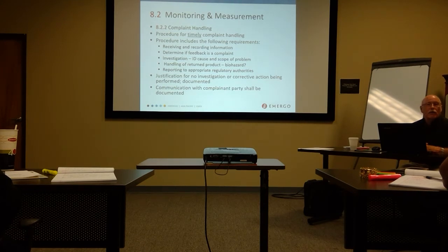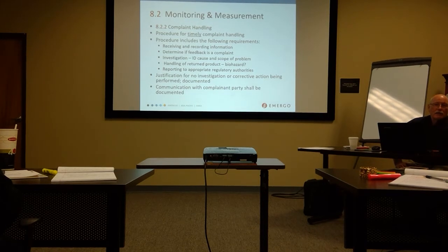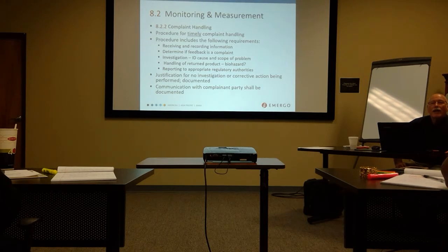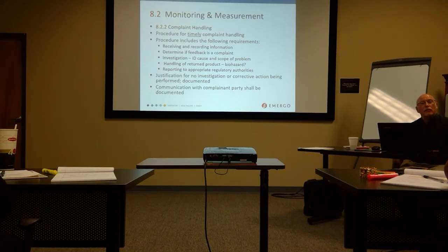Many complaints are due to the user not following the directions. So do you get to discount those automatically? Say, it's a stupid user. Read the bloody user manual. Not necessarily. Track and trend those. Isolated, they mean that the user didn't read the manual, and basically it's their fault. When you get a lot of them, it suggests that there might be problems with the user manual itself. These are still important. You don't mark these as invalid. Track and trend this information, and if appropriate, you react to it.